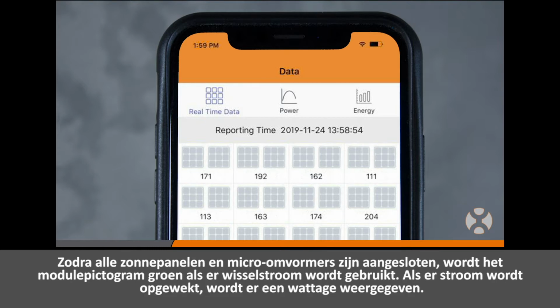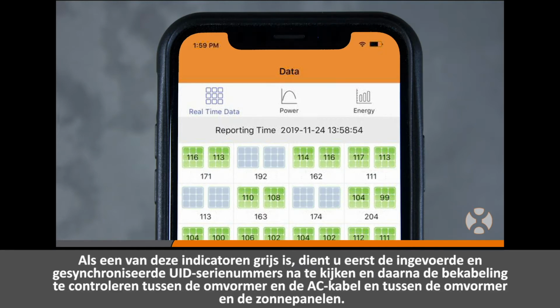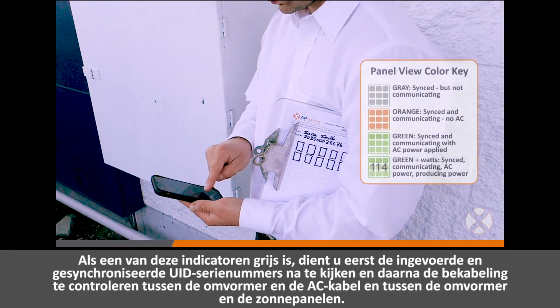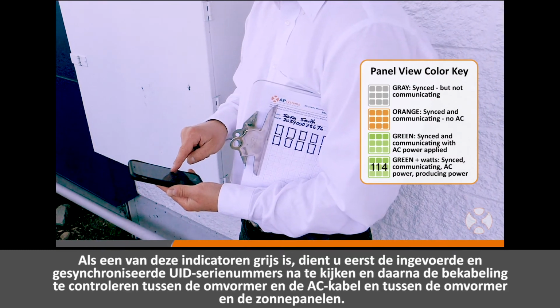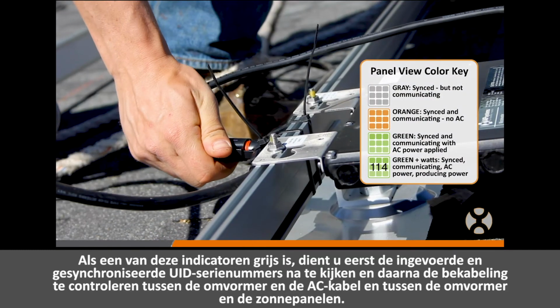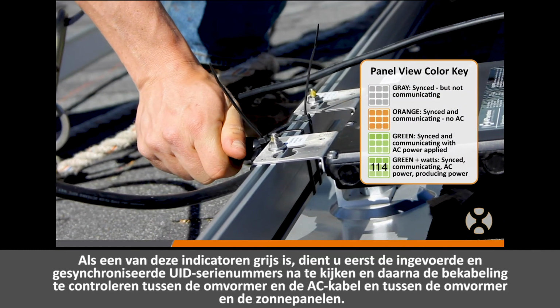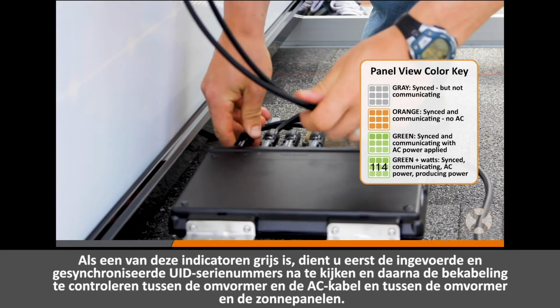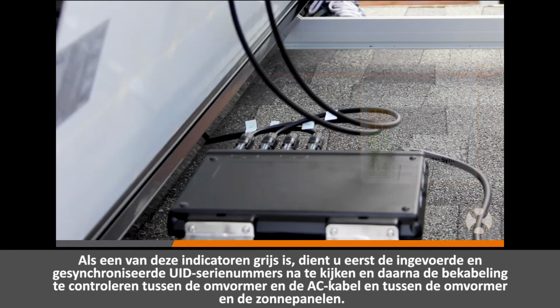Once all the PV modules and microinverters are connected, the module icon will turn green when AC power is applied, and will display a wattage when they are producing power. If any display is gray, the installer should check the UID serial numbers they entered and synced for accuracy, before checking cabling connections between the inverter and the AC bus trunk cable, and between the inverter and the PV modules.